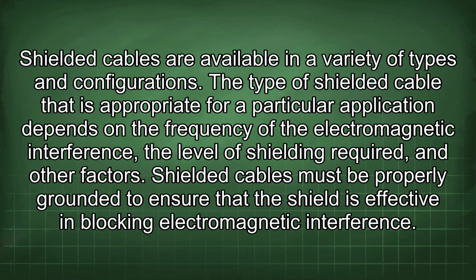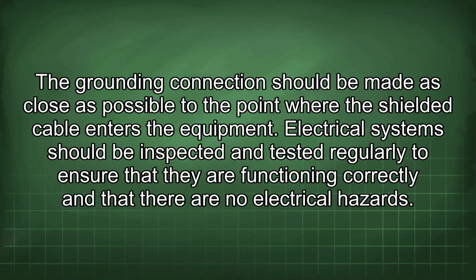Shielded cables are available in a variety of types and configurations. The type of shielded cable that is appropriate for a particular application depends on the frequency of the electromagnetic interference, the level of shielding required, and other factors. Shielded cables must be properly grounded to ensure that the shield is effective in blocking electromagnetic interference. The grounding connection should be made as close as possible to the point where the shielded cable enters the equipment.